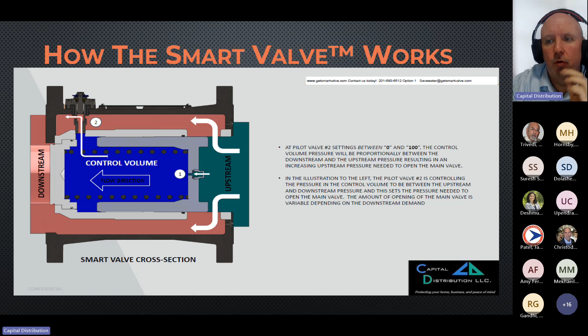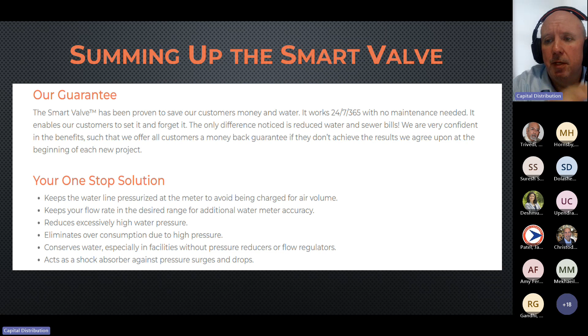So to sum up kind of what I said, it's a 24/7, 365 device. Once it's installed, it's very much set it and forget it. There's no maintenance needed. It can be adjusted post-installation without shutting the water off, doing a shutdown, or removing the valve. Keeps the water line pressurized at the meter to ensure that you're not being charged for air volume. It's going to keep the flow rate in the designed range of the meter so that it operates normally. You're going to reduce any high water pressure, so to increase the life and efficiency of the fixtures.